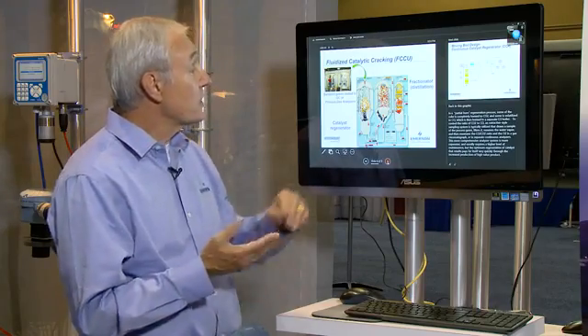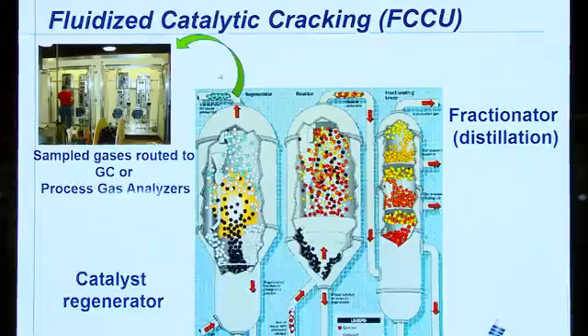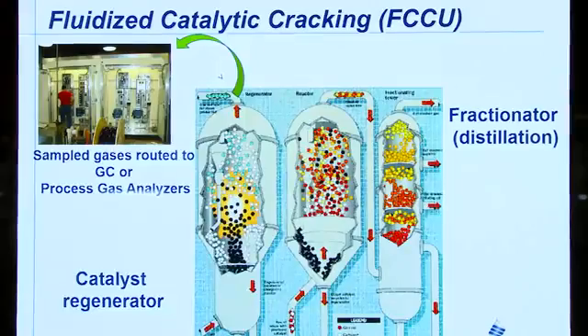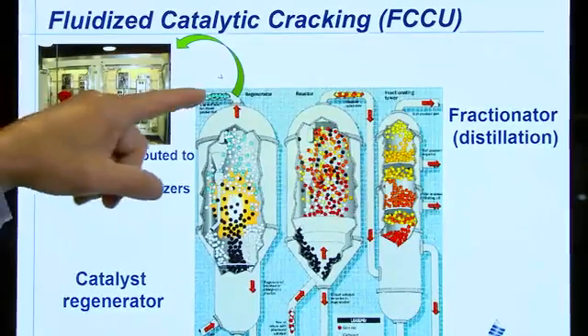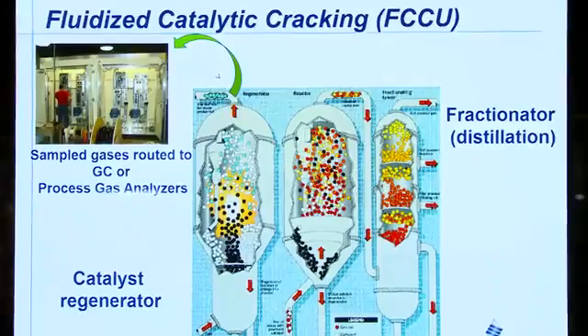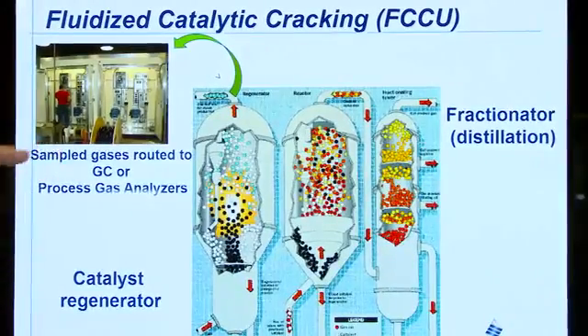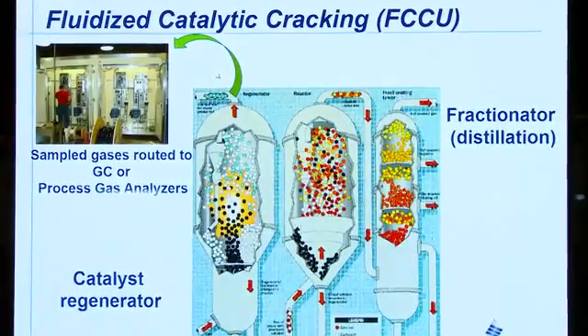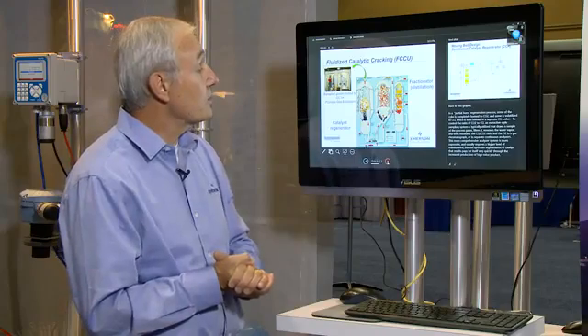So in this process we use an extractive type of system where we draw a sample off, remove the water vapor, remove the particulate, and then place it into analyzers that are usually placed in cabinets or sometimes even a house at the base of the process unit.